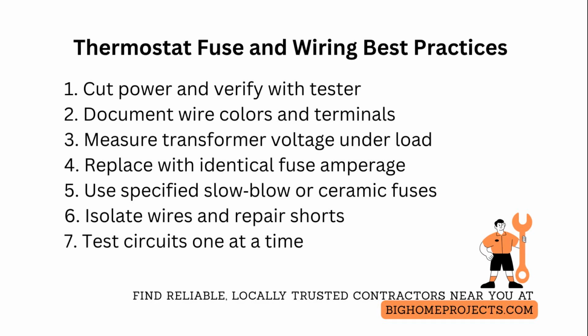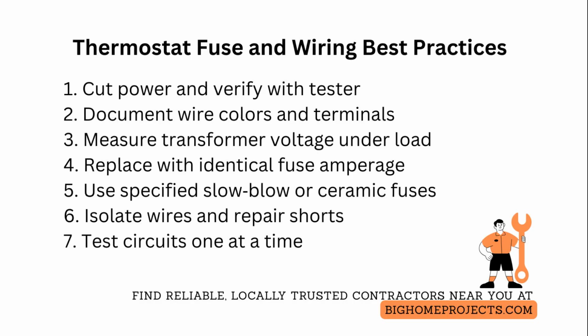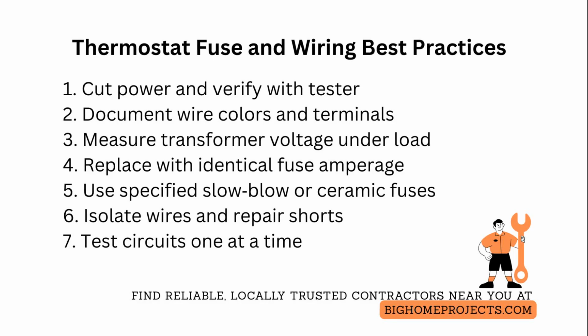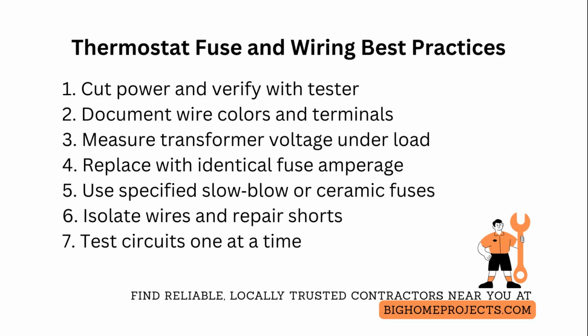Keep a small kit of common replacement fuses labeled by amperage and type and a wiring diagram for the equipment model so you can source the correct part and avoid field substitutions that risk equipment failure. Finally, document the fix, label the thermostat cable at both ends, and advise the homeowner about proper thermostat programming and surge protection to reduce future incidents.